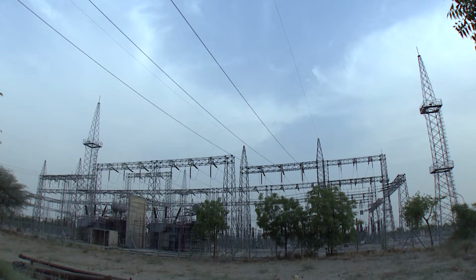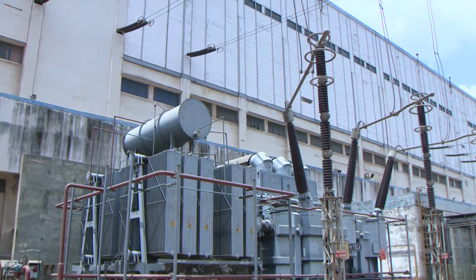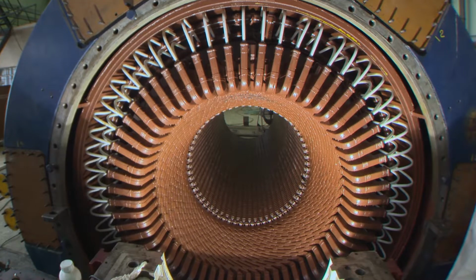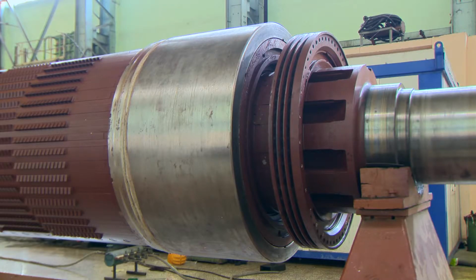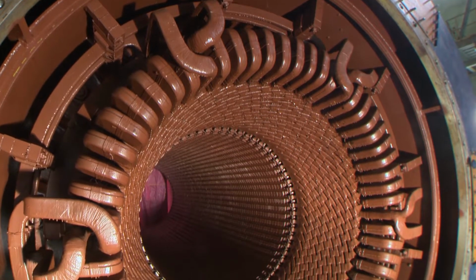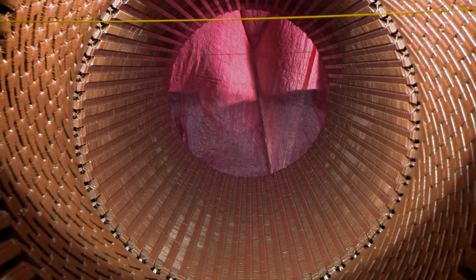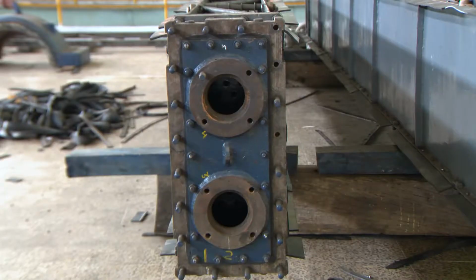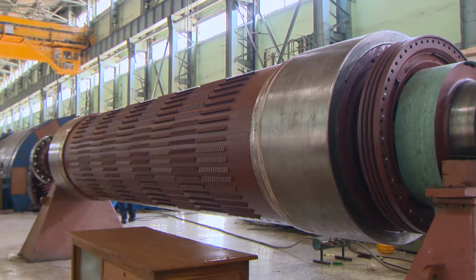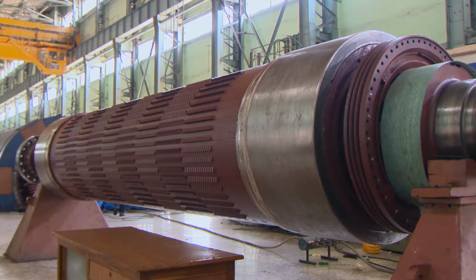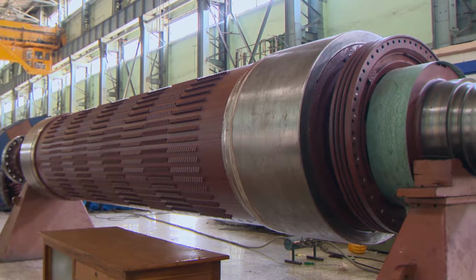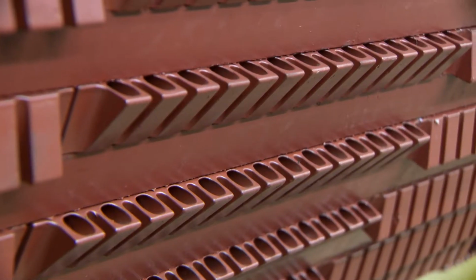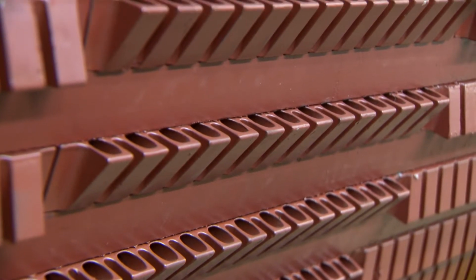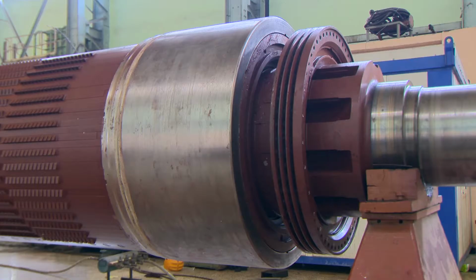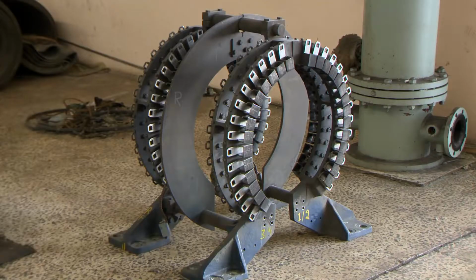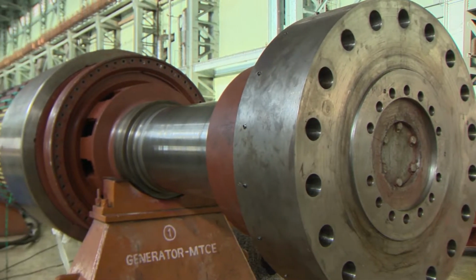The power from the generator is connected to the grid through the generator transformer. The two main parts of generator are stator and rotor. The stator is a stationary part of a generator which consists of stator core, stator winding with hydrogen cooler and terminal bushings. The rotor is the rotating part of the generator which provides the magnetic field and rotates at 3000 rpm. It consists of rotor winding slots, ventilation ducts, retaining ring, cooling fan, slip rings, brush gear assembly and coupling.